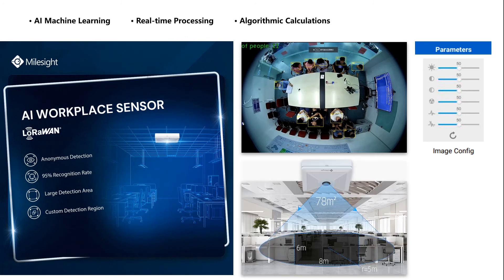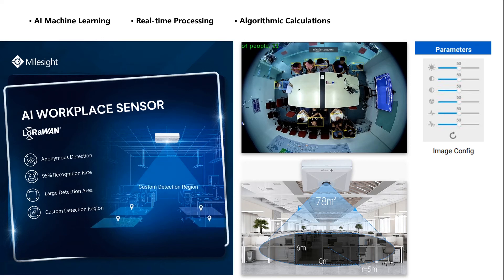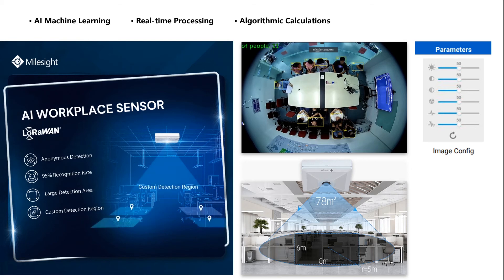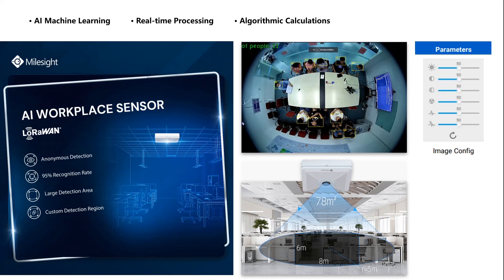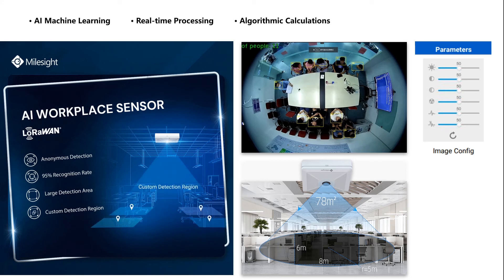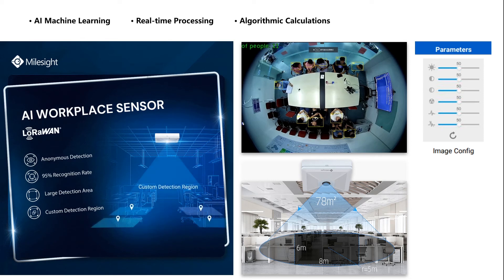Some of you may wonder how we manage open areas and workstations. This sensor is threshold-based. We trace open areas by creating abstract thresholds, similar to doors. Through AI machine learning, we wrote an algorithm that analyzes people moving through that threshold. In the same way a human could spot what a person is — as opposed to a desk or a dog — the system watches that person go through a threshold. If successful, it tells our server that a count just happened.